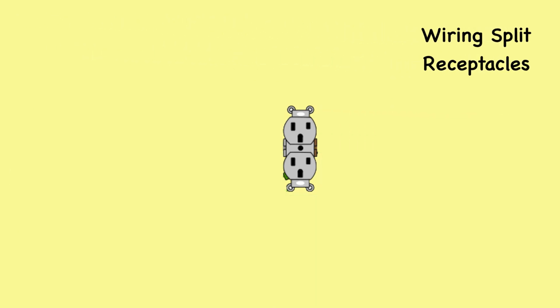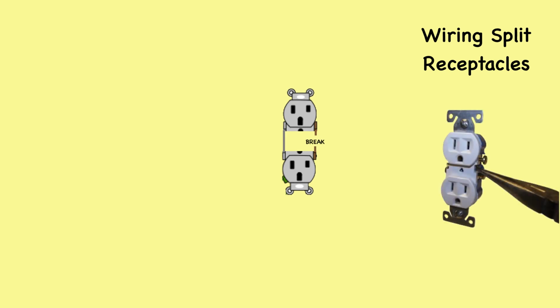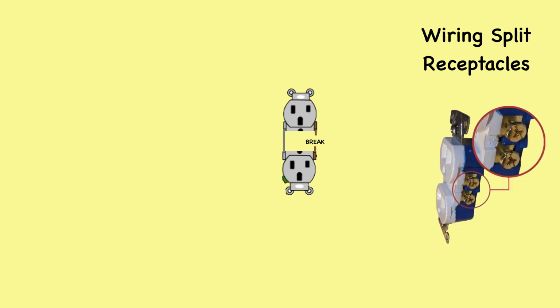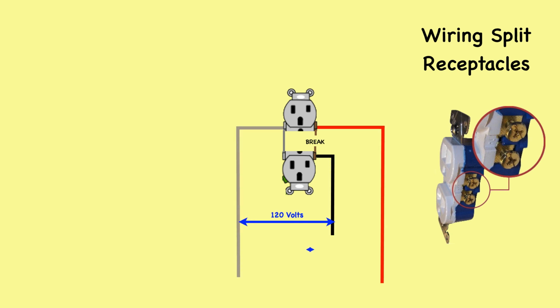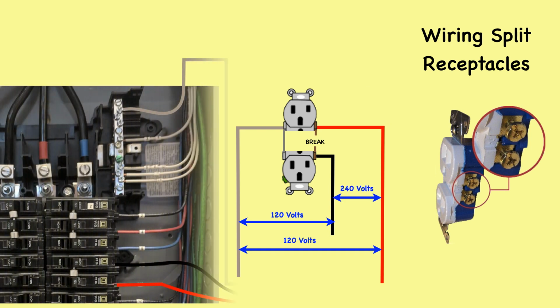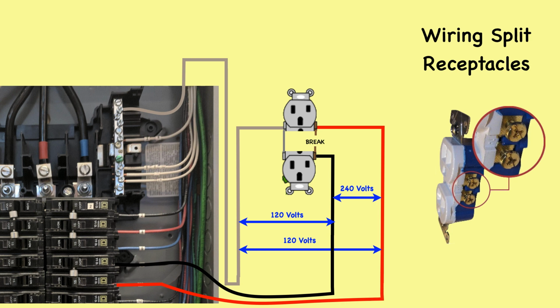This graphic dramatically shows what happens with a split receptacle. Breaking the connecting bar between the two brass or hot screws of the receptacle electrically separates the bottom from the top of the plug. The red and black wire each carry 120 volts to neutral to each of the plugs, even though the potential difference between the red and black wire is 240 volts. This is because the red and black wires are connected to a double pole single throw 15 amp breaker back at the service panel.